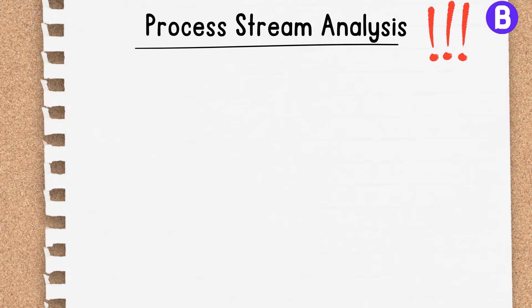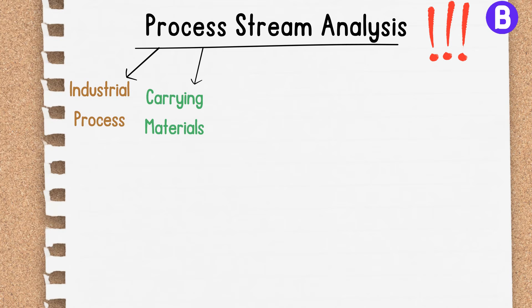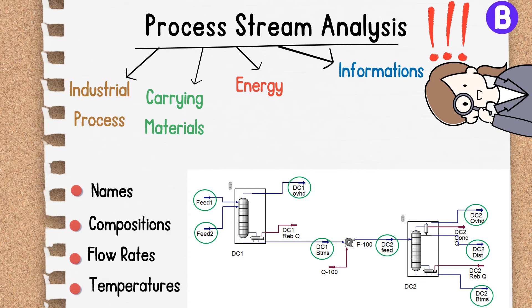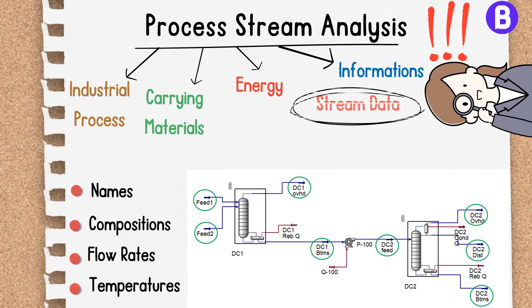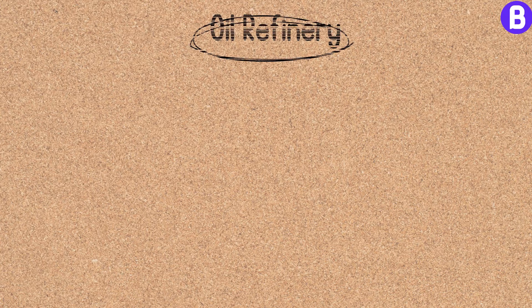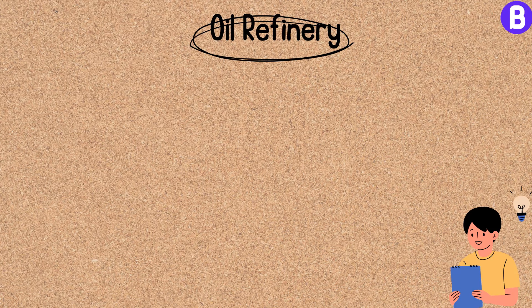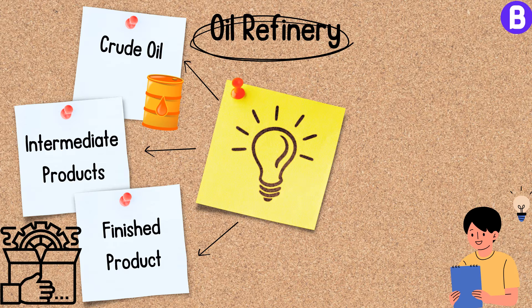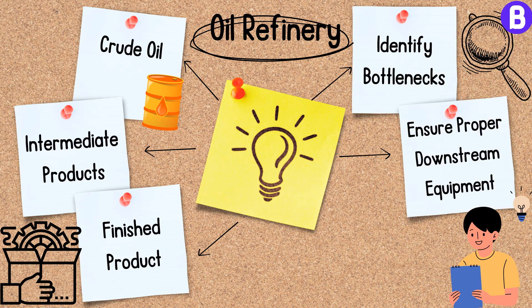Process streams are the lifeblood of any industrial process, carrying materials, energy, or information throughout the system. A well-constructed PFD provides detailed information about the main process streams, including their names, compositions, flow rates, and temperatures, usually accompanied by heat and mass balance tables. For example, in an oil refinery PFD, streams such as crude oil, intermediate products, and finished products are displayed, helping identify bottlenecks and ensure proper downstream equipment and pipe sizing.